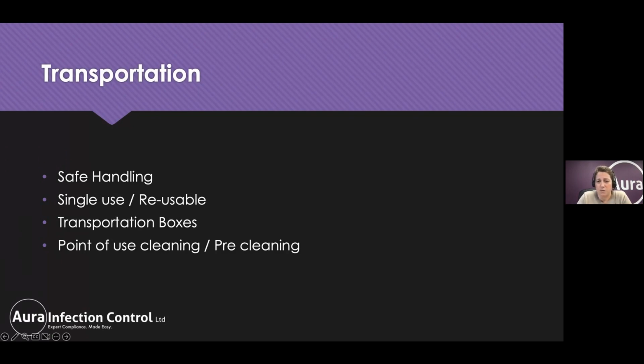Now, we want to make sure that we're moving them without delay because any drying time is going to have a negative impact on the ability to have successful cleaning and decontamination. So we know that proteins are going to bond onto metal when you heat it above 45 degrees, but proteins will also bond onto metal and become quite sticky if you leave them to air dry for 30 minutes, 45 minutes. The longer they dry, the harder it is to remove that contamination. So moving them without delay is important.